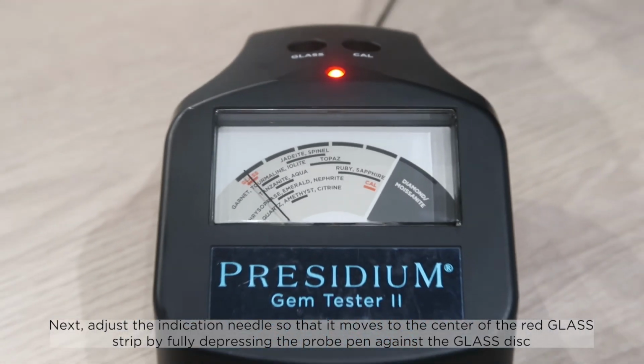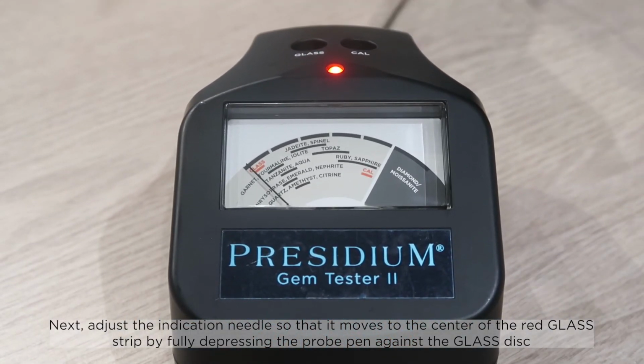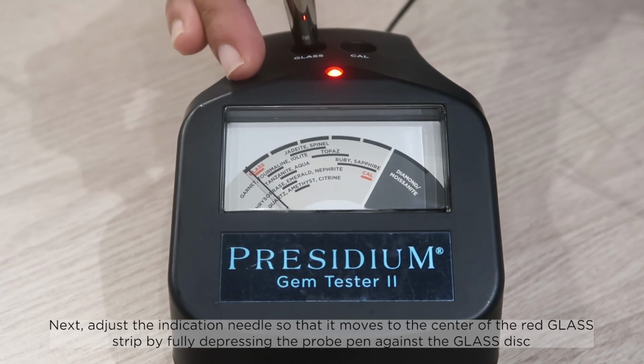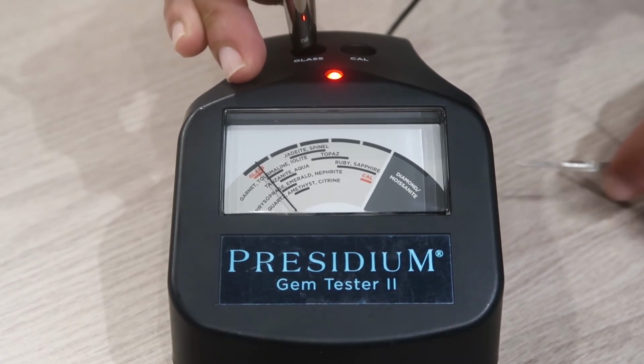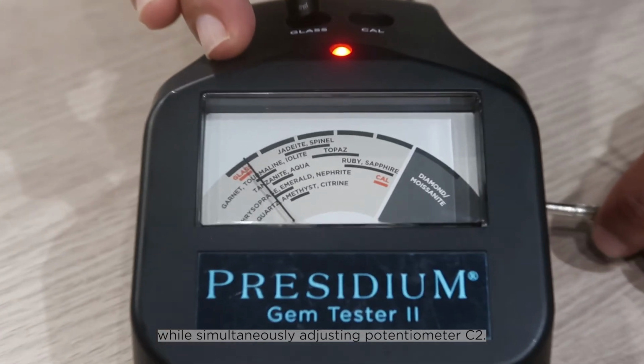Next, adjust the indication needle so that it moves to the center of the red glass strip by fully depressing the probe pen against the glass disc while simultaneously adjusting potentiometer C2.